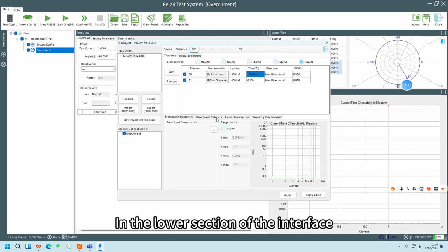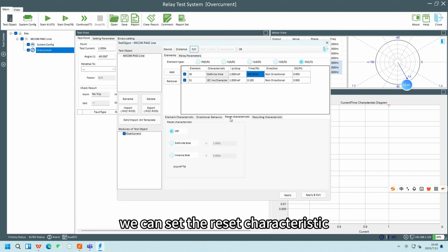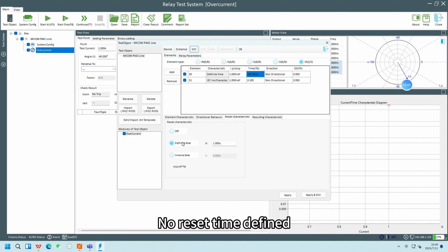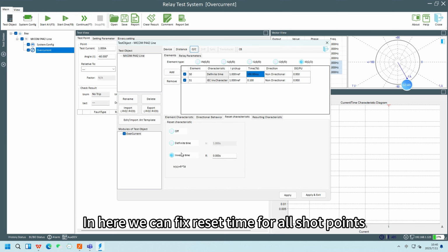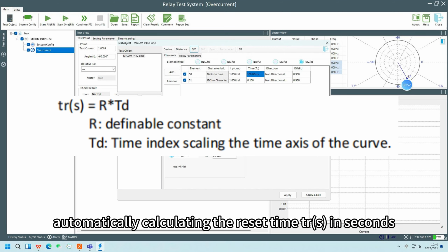In the lower section of the interface, we can set the reset characteristic. When we turn the reset characteristic off, no reset time is defined. Definite time, in here we can fix the reset time for all shot points. Inverse time, automatically calculating the reset time in seconds.